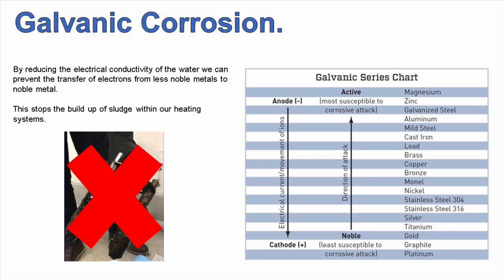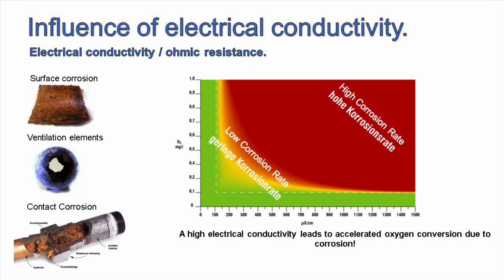Galvanic corrosion is when you have a noble metal and a less noble metal. The less noble metal transfers its electrons through the water. So the water is our reaction agent, our electrolyte, and it's passing electrons to the more noble metal, which would be a cathode. In doing so, the less noble metal gets attacked by any oxygen in the system. So if we have a low electrical conductivity, we're reducing the path for electrons to move from one metal to another. Even in the presence of oxygen, having a low conductivity essentially reduces our risk of corrosion within our system. So we reduce the mineral content, which reduces the conductivity, which gives us a system where corrosion is very unlikely.